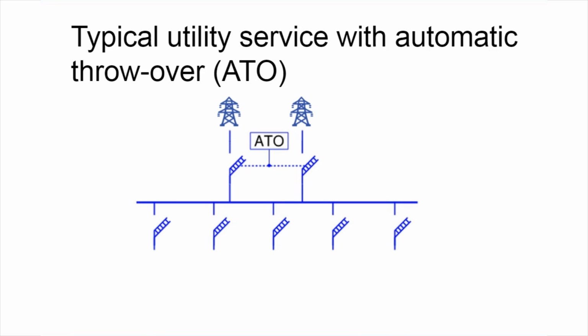This is an example of a typical utility service with automatic throwover. Here we see two separate utility feeders coming into the site, and an automatic throwover switch. If either one of those services goes down, power is restored automatically to the alternate source. And when it's restored, it will supply the entire bus of medium voltage feeders throughout the campus.